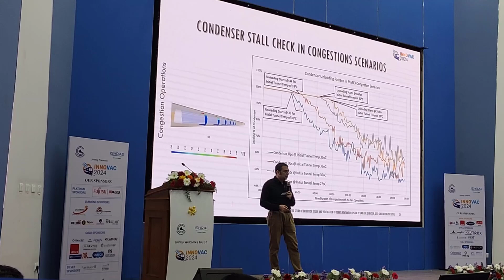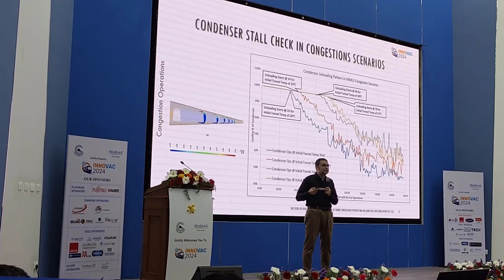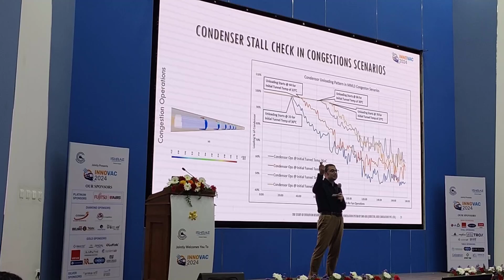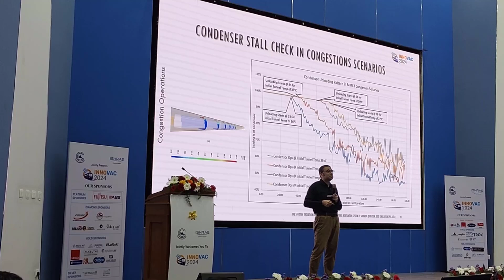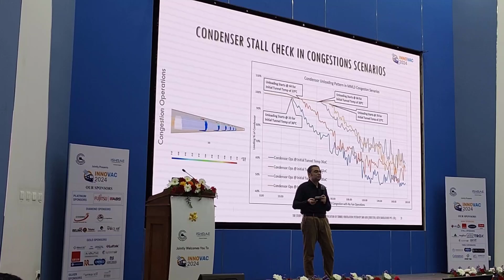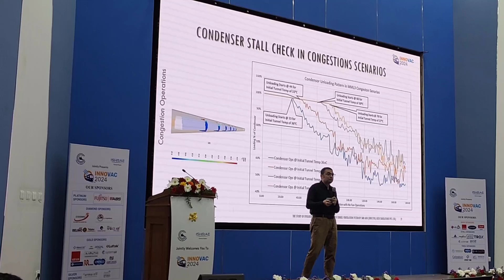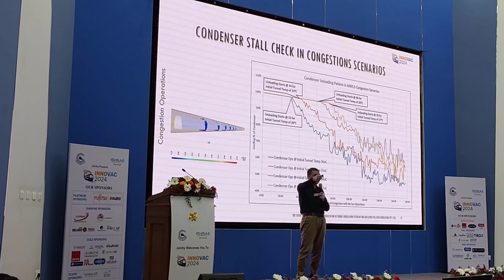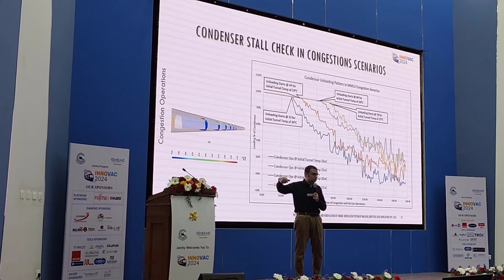This is with respect to congestion. Your coaches are air conditioned, and you never felt that the air conditioning is not working. But imagine the train is stuck for say 10 or 15 minutes in the tunnel. Your air conditioning system, by virtue of its design, rejects the inside heat to the outside. In case the outside temperature goes beyond say 60 or 65 degrees centigrade, your air conditioning system is going to fail. So what you do is design your ventilation system to ensure the tunnel temperature doesn't go beyond a certain point, and as soon as this congestion situation comes up, you supply your ventilation system.